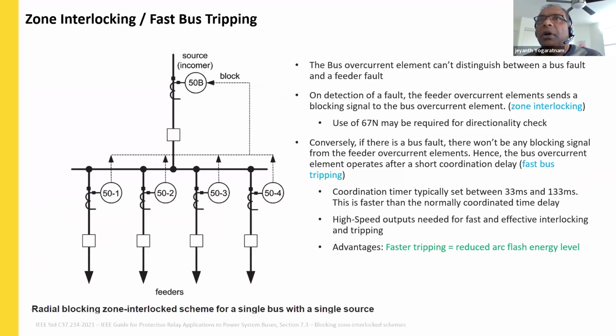The other application I wanted to talk about is zone interlocking. This is very straightforward, so let's study this circuitry. There is a feeder feeding the bus, and there are 4 radial feeders feeding the loads. We have a protection device at the feeder feeding the bus, which is called the source relay, and we will identify the feeder feeding the load as the load feeder. If there is a fault at the load side, then both relays, the relay at the source and the relay at the radial feeder, will see it. We need to discriminate here, because we want to keep power to as many loads as possible and only remove the faulty feeder.